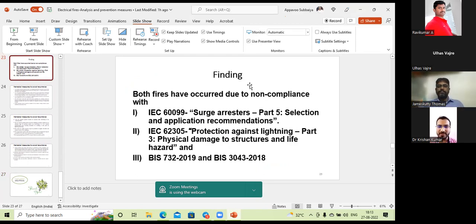Actually, I'm working with a company which works on lightning protection. I always calculate risk due to lightning. When I calculate the risk to a particular structure, there is a factor we have to consider, the risk of fire. And I always get confused about what I should consider: a low, high or medium risk of fire. Because the standard gives it in the form of energy, let us suppose 100 megajoule per square meter will be released when a fire occurs to that particular material in the structure. So sir, is there any standard where I can find that this amount of energy will be released by this material and that amount by another material? How can I differentiate between low risk of fire and medium risk of fire for a particular structure?